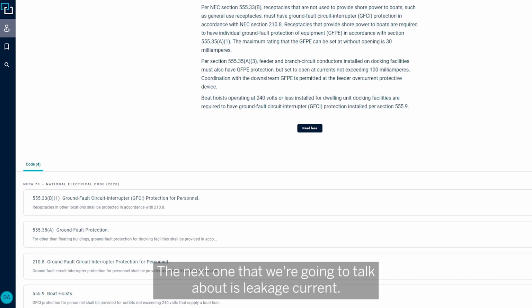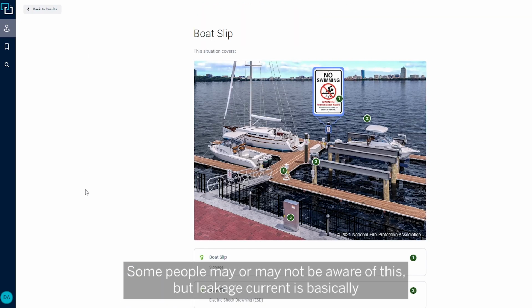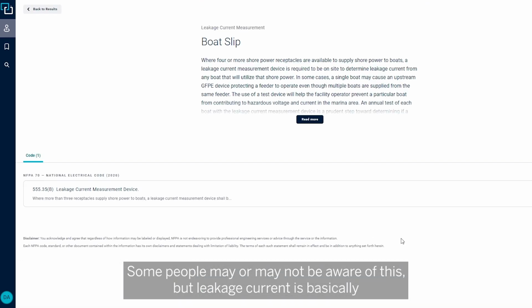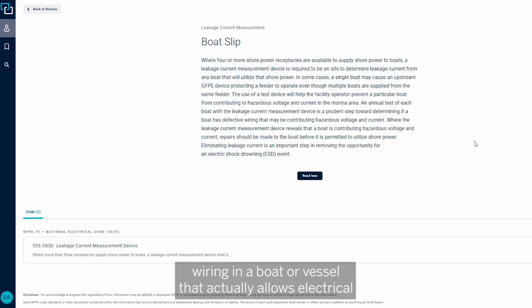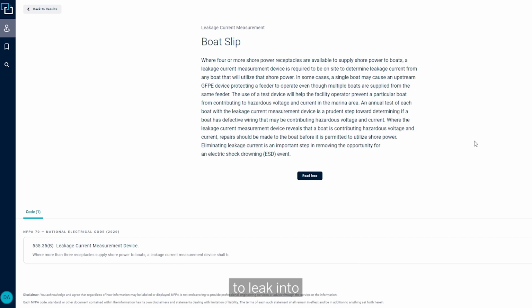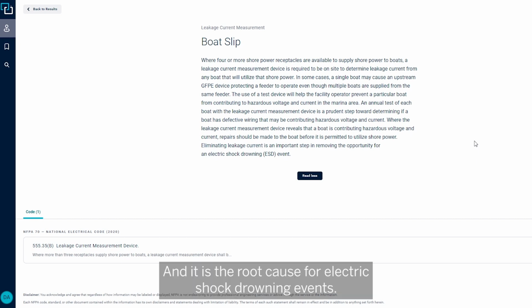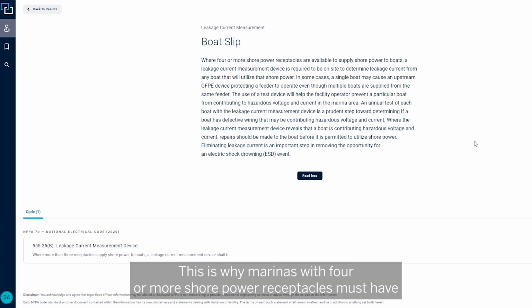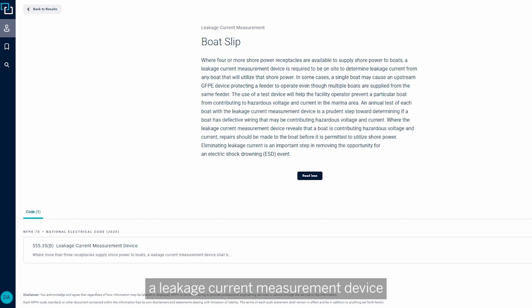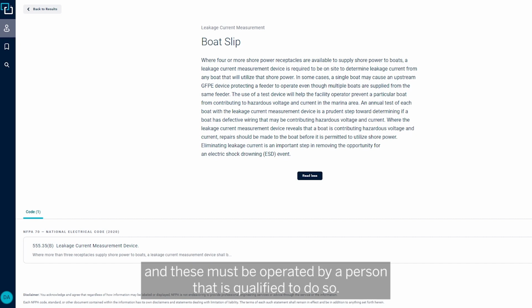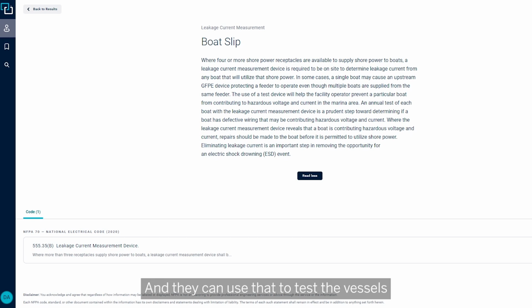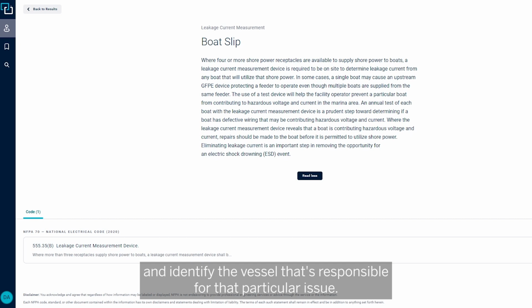The next one that we're going to talk about is leakage current. Some people may or may not be aware of this, but leakage current is basically an event that happens due to defective wiring in a boat or vessel that actually allows electricity to leak into the water and charge that water, and it is the root cause of electric shock drowning events. This is why marinas with 4 or more shore power receptacles must have a leakage current measurement device to test vessels for leakage current. These must be operated by a person that is qualified to do so. They need to know how to use it, and they can use that to test the vessels and identify the vessel that's responsible for that particular issue.